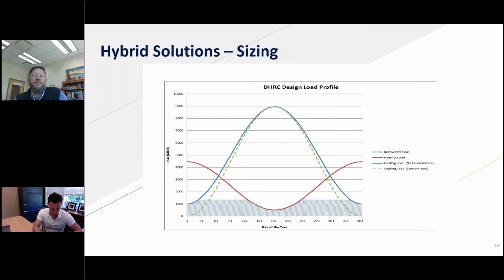Okay, so that gray shaded area, that in and of itself is an opportunity to either ensure we have an air source heat pump that can do simultaneous or heat recovery, or if we can't, that we can divorce that from the air source heat pump. We can say, hey, if that's 30 tons or 50 tons or 100 tons or 500 tons, depending on the size of our plant, I can dedicate a heat recovery chiller to just doing that based on what my full simultaneous year-round load is. So not only do we get more efficient, but if we're going to remove it from the air source heat pump plant, well, now I can put my heat recovery chiller inside the building. One of the things we're running into now, and we will continue to run into, is roof space.